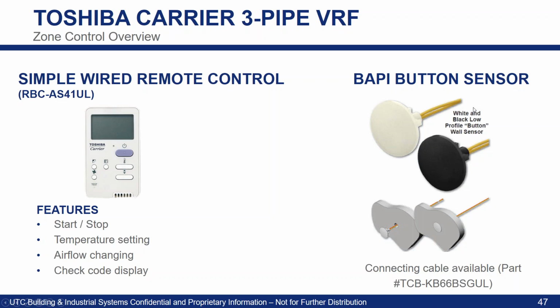Also some button sensors if you're not looking to give any control at all to the user. Really, you don't even need these because each fan coil is going to have a return air sensor, obviously, and we can set the system up to control per return air temp at each fan coil.